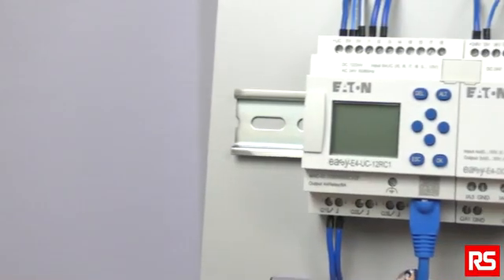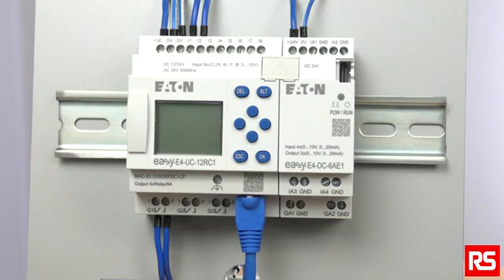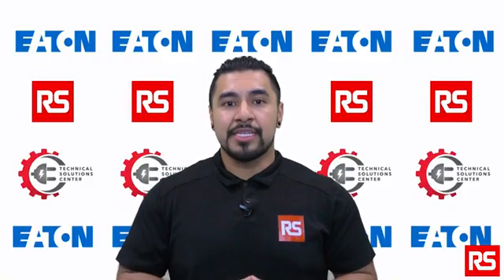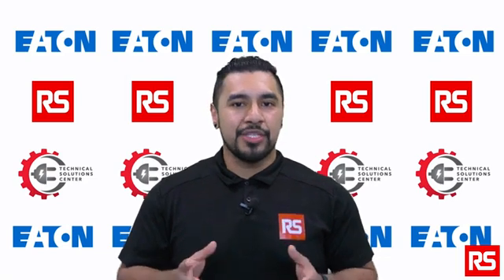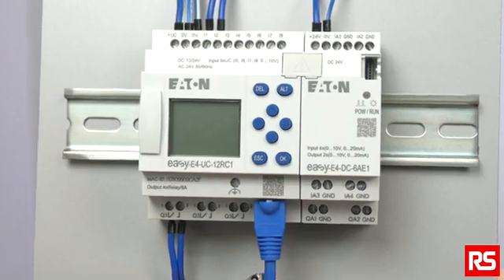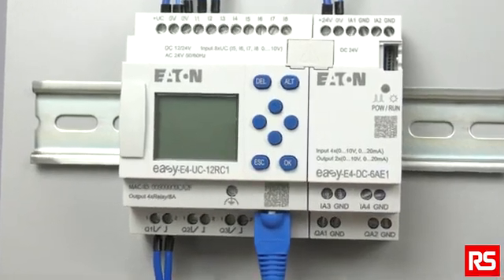To mount the easy-E4, install it in an enclosure, switch cabinet, or distribution board so that the power supply and terminal connections cannot be touched accidentally during operation. The easy-E4 can be mounted either vertically or horizontally, and for ease of wiring, be sure to leave a clearance of at least 3 cm between the device terminals and the wall or adjacent devices.